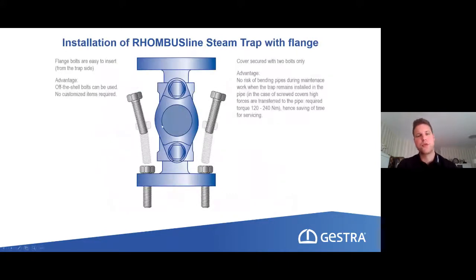This is what I mean. When it comes to easy installation, in the past we had a body of a steam trap which was squared, and it was not possible to access the screws in the flange connection. So there was only one way to exchange the steam trap if it had to be replaced. You had to use a saw to saw through the screws, and only then was it possible to exchange it. But now it's much easier, by just taking out the screws that way.